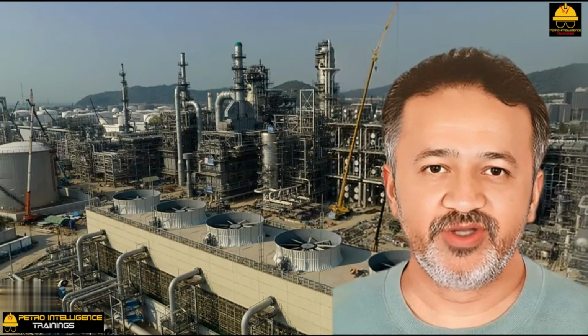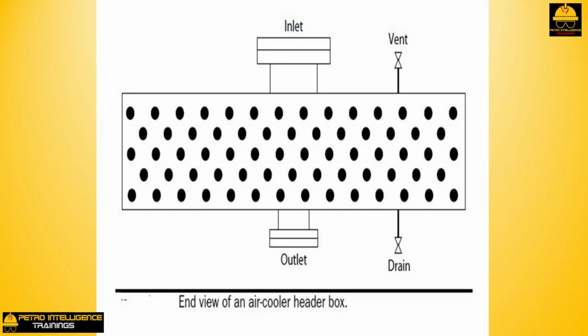Tube side construction. The mechanical construction of the tubes in an air cooler creates some rather nasty problems. Picture shows the exterior appearance at either end of an air cooler. The small black circles are threaded steel plugs. They are not connected to the ends of the tubes.